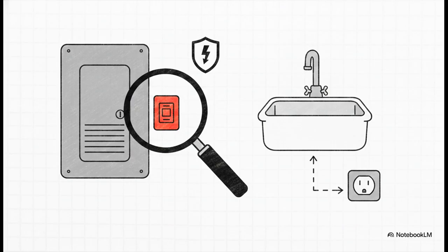So who's the prime suspect? Well, it's sitting right there in the electrical panel, a brand new 50-amp GFCI breaker. Now, because this user was switching from gas to electric, new wiring had to be run. And because this new stove outlet was located within 6 feet of the kitchen sink, modern electrical code legally required the use of a GFCI breaker to protect against electric shock. It's a safety device, right? It's doing exactly what it was designed to do. But as you'll see, it might be doing its job just a little too well.